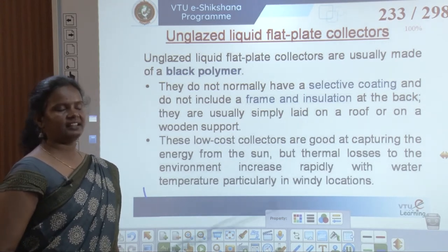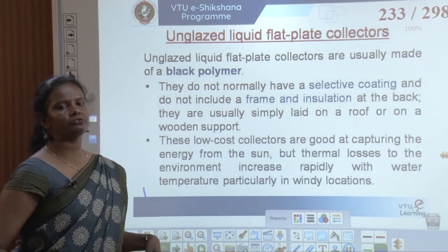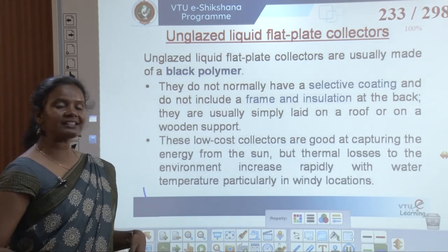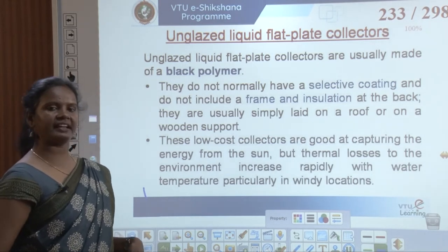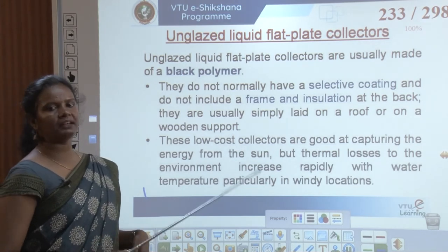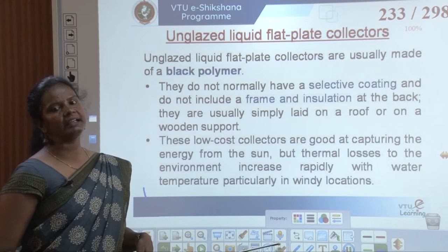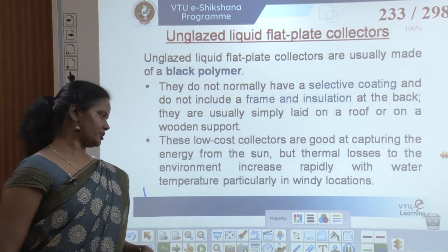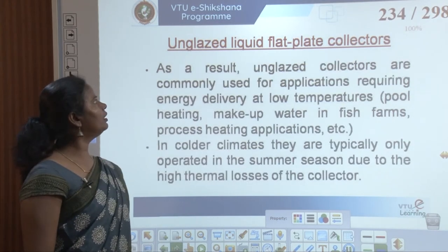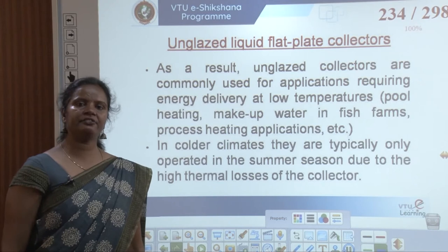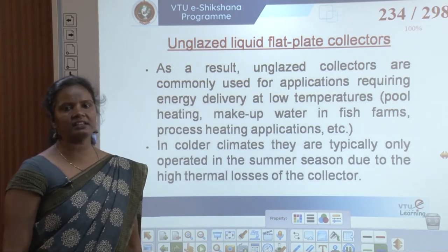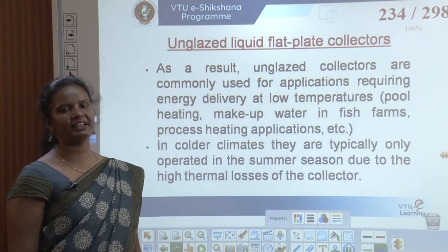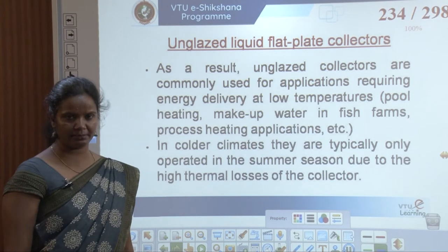These low cost collectors are low cost because they don't have other facilities like covering, coating, etc. These low cost collectors are good at capturing the energy from the sun, but thermal losses to the environment increase rapidly with water temperature, particularly in windy locations. As a result, unglazed collectors are commonly used for applications requiring energy delivery at lower temperatures.